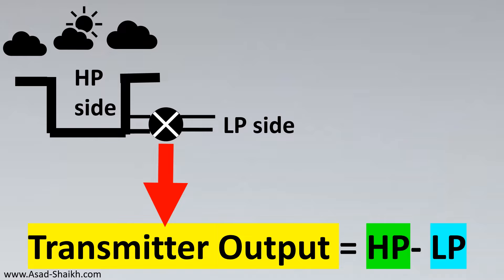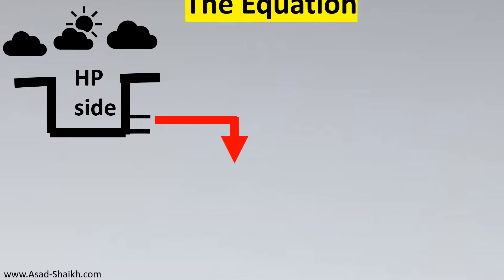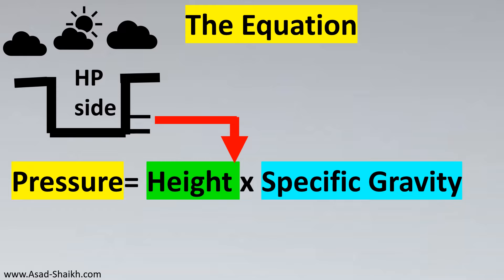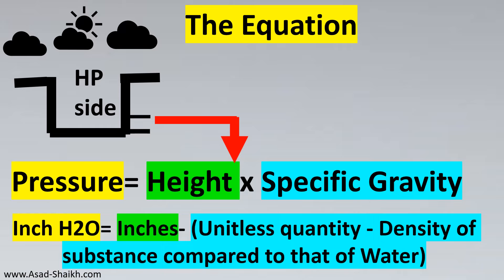Now we look into what equation we can use to calculate pressure. Pressure is equal to height multiplied by specific gravity. The pressure is in inches of H2O, the height is in inches, and specific gravity is a unitless quantity — it is simply the density of a substance compared to that of water. Multiplying by inches gives pressure in inches of H2O. Had the height been in mm, the output would have been in mmH2O.